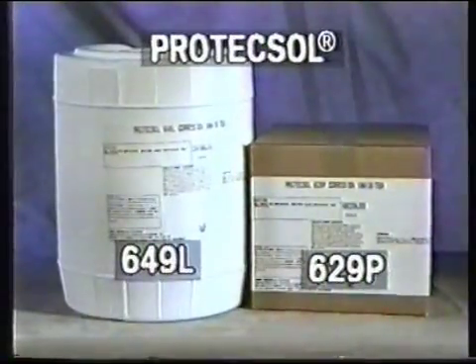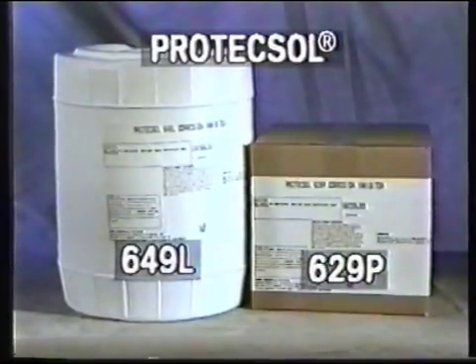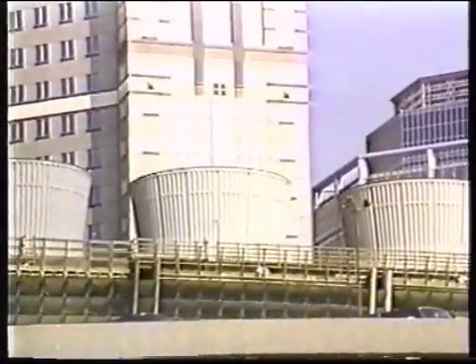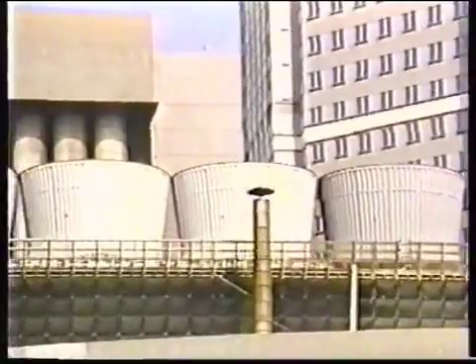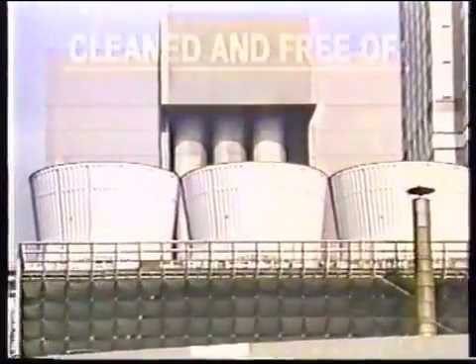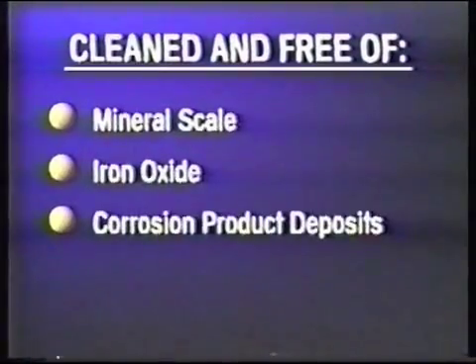Protecsol 649L and Protecsol 629P are additional corrosion inhibitor products included in the investment protection program. Both products are especially designed for wet and dry layup of cooling systems. It is important to note that prior to initiating any layup procedure, the cooling system should be cleaned and free of mineral scale, iron oxide corrosion product deposits, and bacterial contamination.